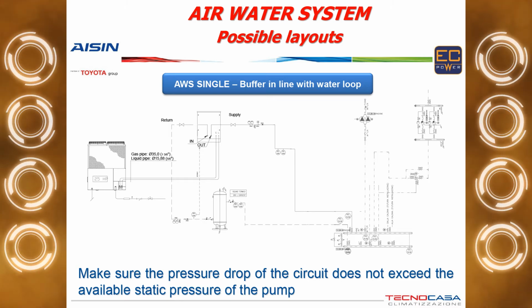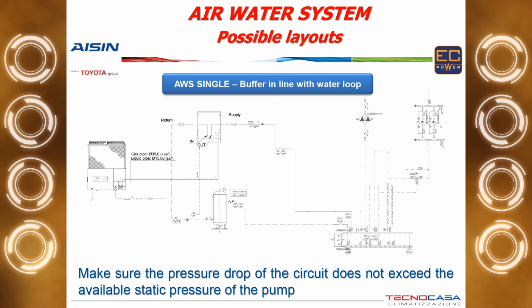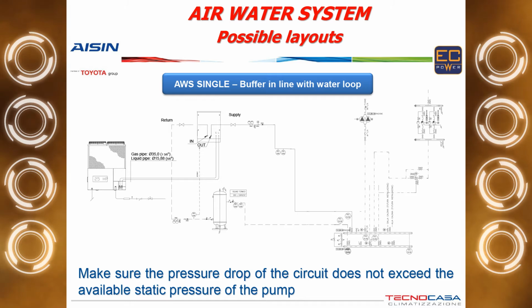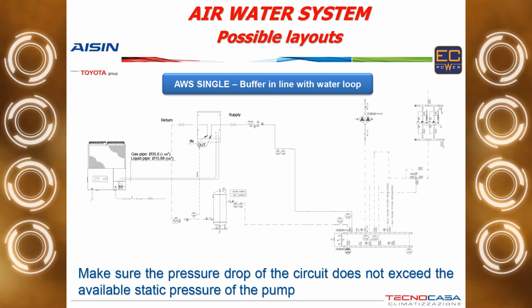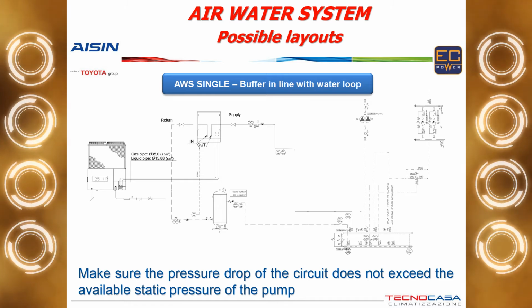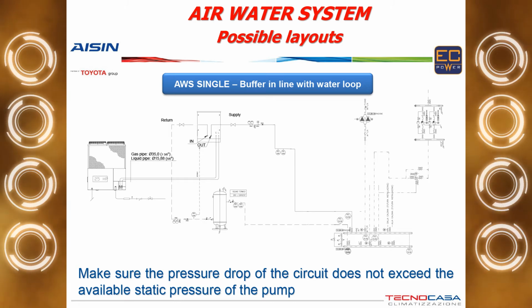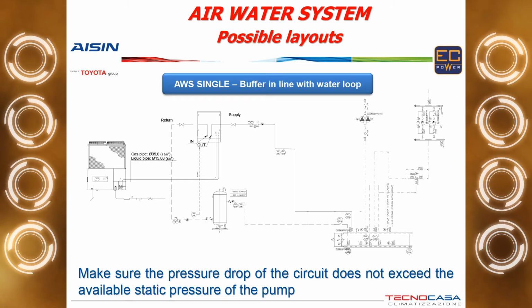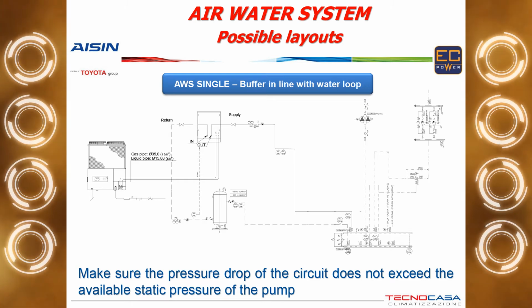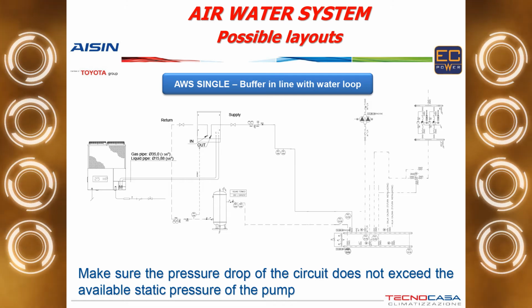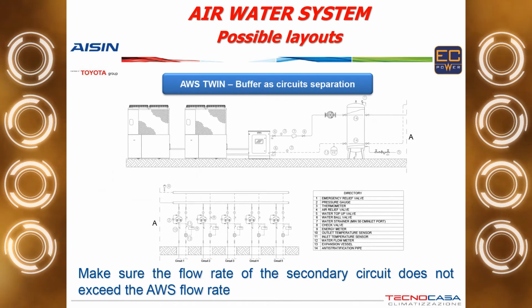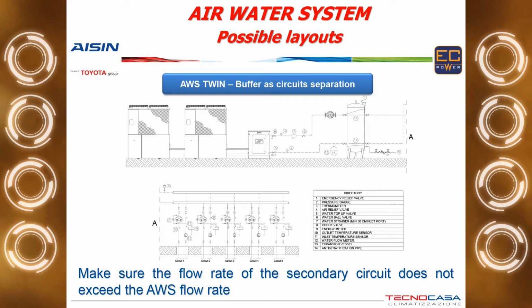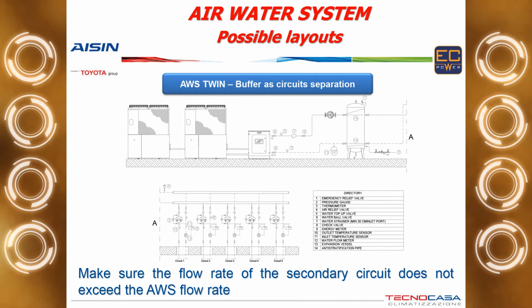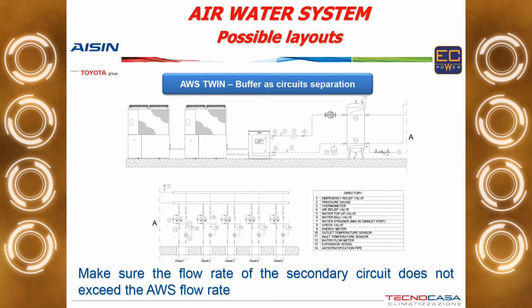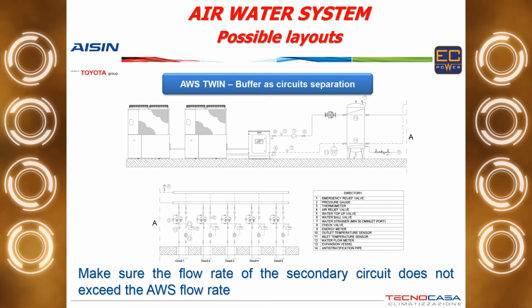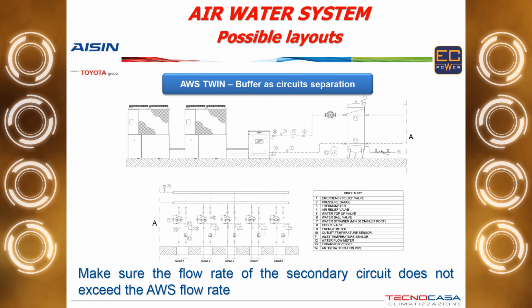In this case, you have to make sure that the pressure drop of the circuit does not exceed the available static pressure of the pump, which is built in the system. Otherwise, we can provide an air-water system without pump, and you can select the pump of your choice, which is able to move the water everywhere in the system without losing any pressure. This is the other possibility where we can combine 2 GHPs in one air-water system, and in this case the buffer tank is also the hydraulic separator between the primary and the secondary system.